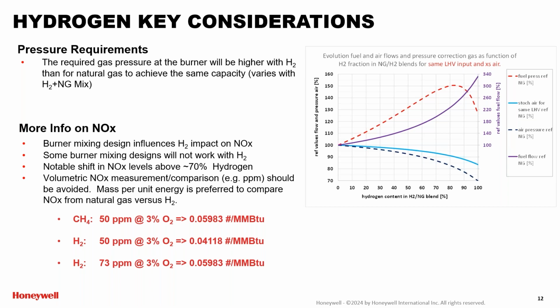And that comes really from the lesser volume of your POCs. You'll require less volumetric stoichiometric air, and the physics make that change pretty significant. So this is something that in the future, I'm hoping, because this always goes to contention, right? In most burners, NOx goes up as you turn the burner down, some more significantly than others, depending on the type of burner and its intended application. But in pounds per million, as your firing rate goes down, your mass is going down. So it really should come down to, hey, what are you actually releasing into the atmosphere? It's a tightrope that we are on sometimes, so it'll be interesting to see where the industry goes in terms of measurement of NOx and how we record that.